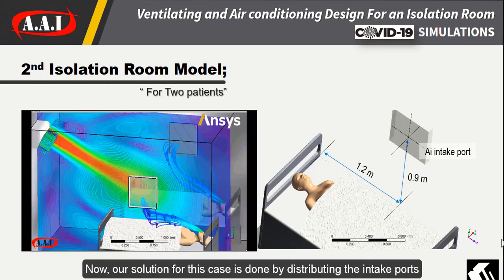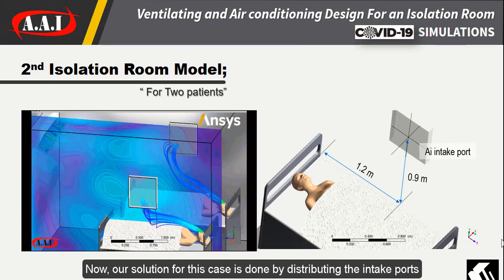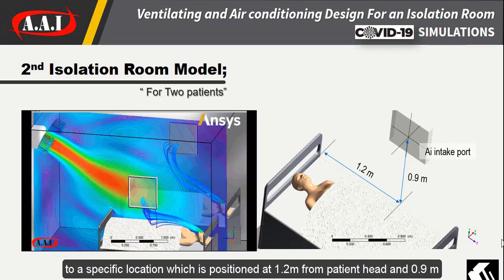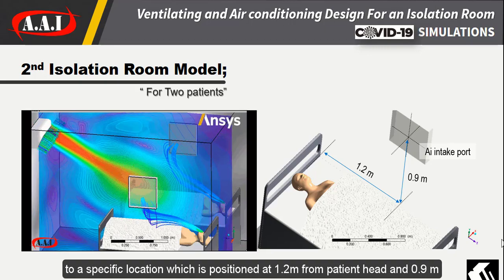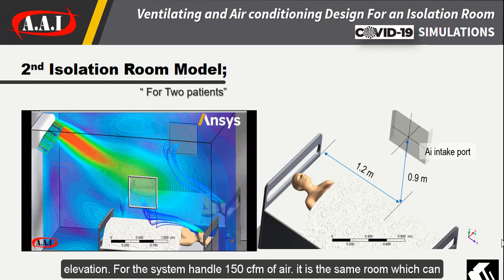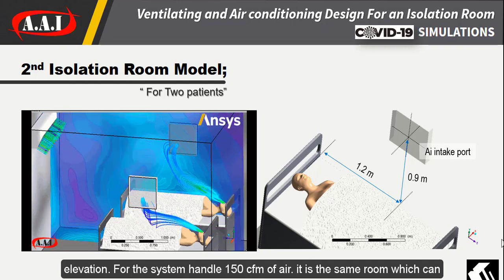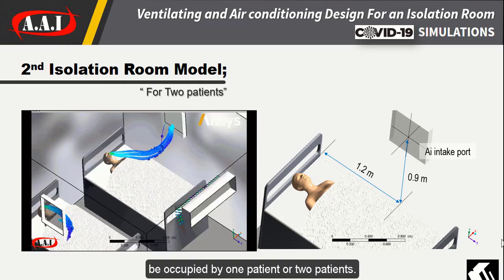Our solution for this case is done by distributing the intake ports to a specific location positioned at 1.2 meters from the patient's head and 0.9 meter elevation, for a system handling 150 CFM of air. It is the same room which can be occupied by one patient or two patients.